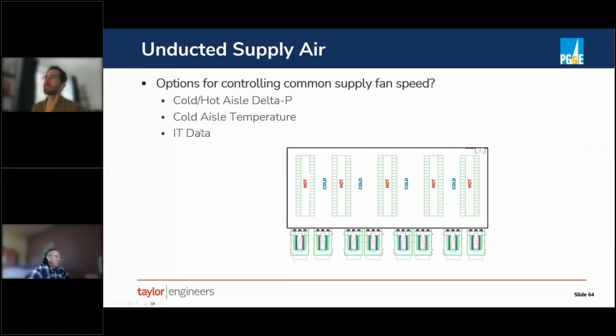And we haven't had much success with this, but we've been trying for many years to get feedback on the data from the computers to the mechanical system. You would think that's not such a difficult thing, but the computers are not on the same sort of network, if you will. Transferring data on temperatures and flow rates is hard. There are a lot of sensors on each server and a lot of data available, but it's not been easily communicated between the IT and the mechanical system. But if you had that data, then you wouldn't necessarily need any of your own sensors in the cold aisle, because every server could tell you what temperature was coming out of it.